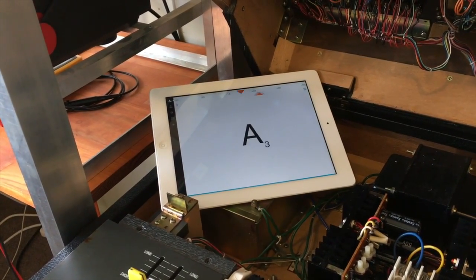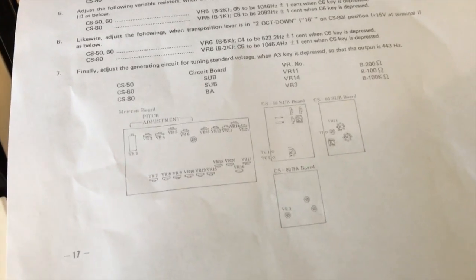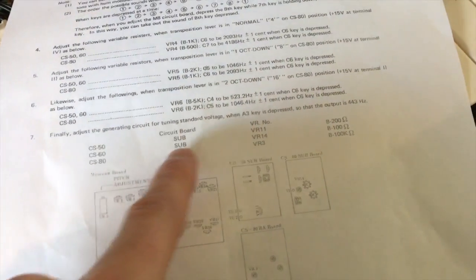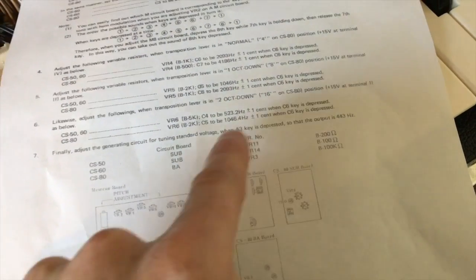Wow, that's close. That's really close. I may not even do this adjustment. It's just on that subboard, and it's VR14. Where are we? CS-60, VR14. Adjust to get A. But it's already in tune. So I think I'm going to leave it there. And we're done! Yes! We've done the whole voice calibration. That's awesome. We can go back to the normal part of the manual.